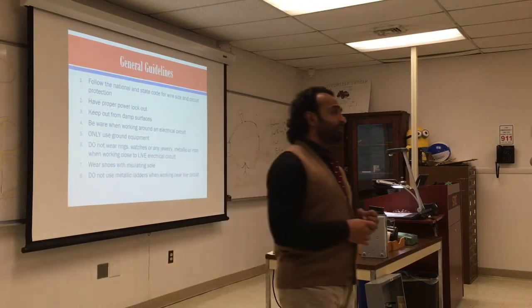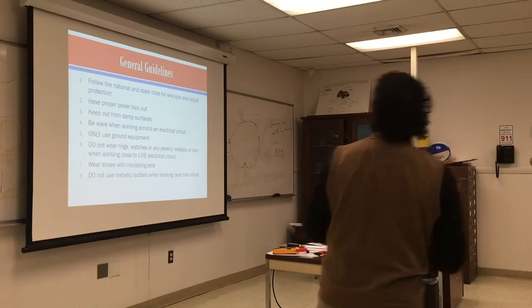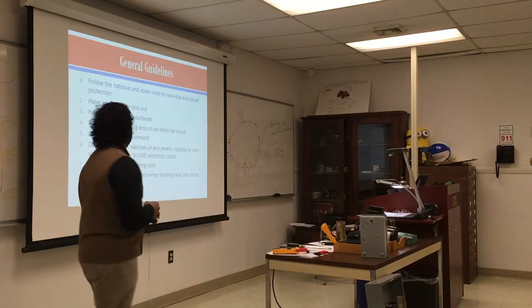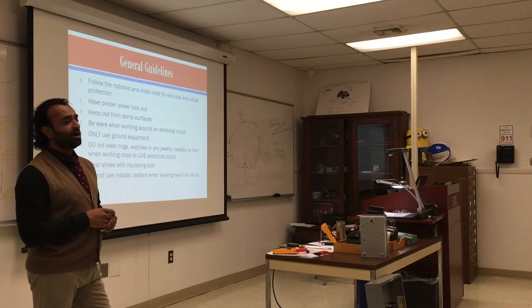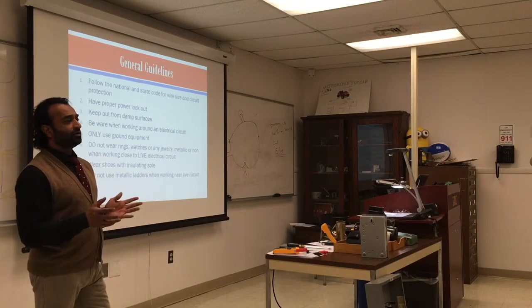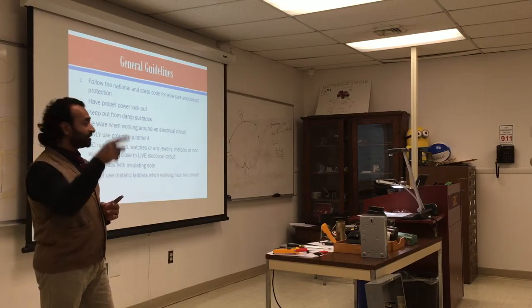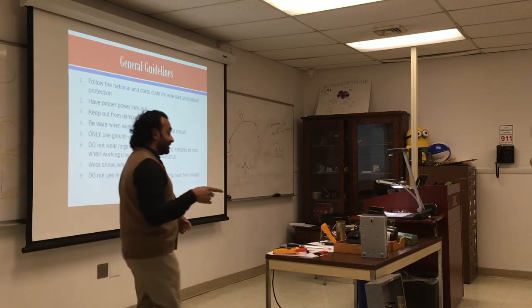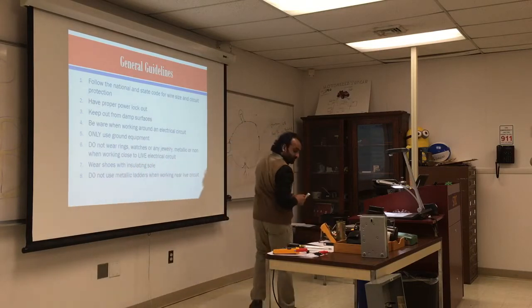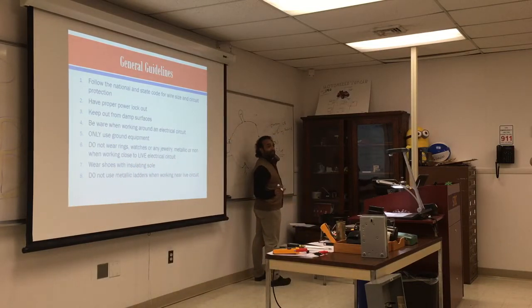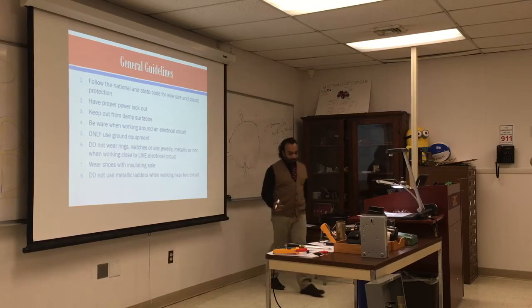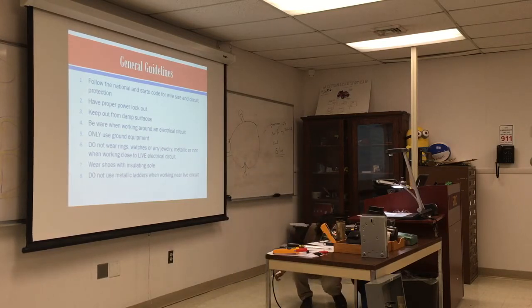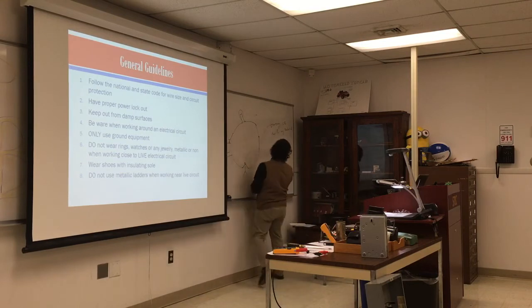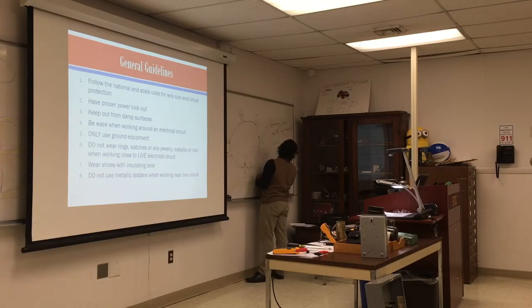Meaning the size of the circuit breaker, the size of the fuse, and wire size. What is the standard wire size gauge for most HVAC equipment? 14 - let's remember that. It was 5 years ago it was 16, now it's 14. And 14 goes along with 15 amps - 15 amp circuits require 14 gauge. Okay, American wire gauge 14.